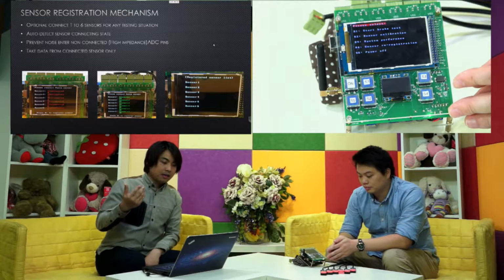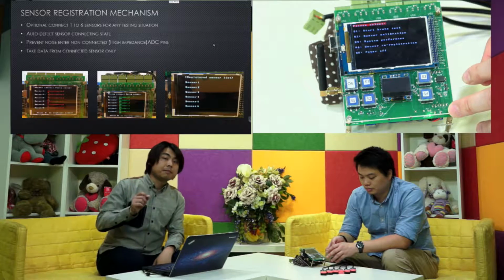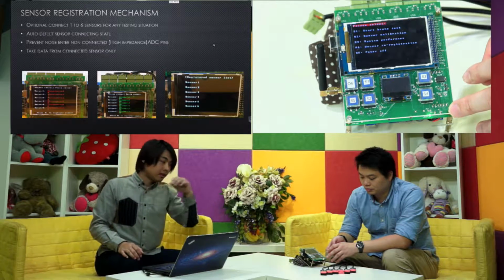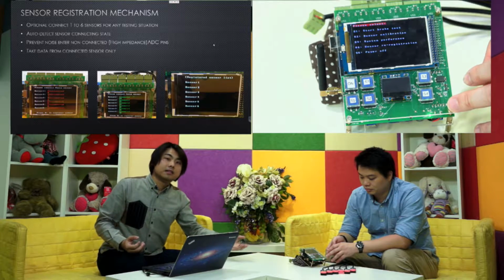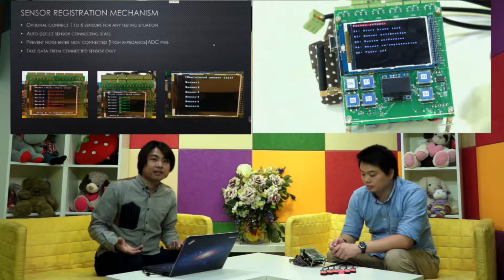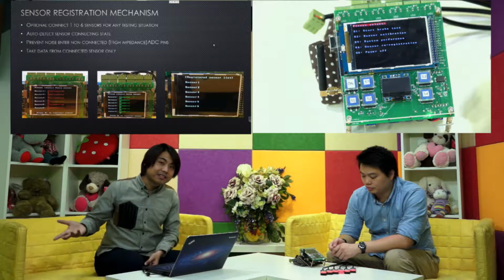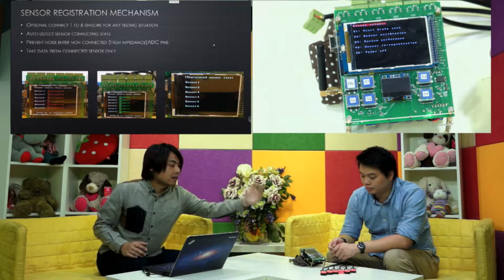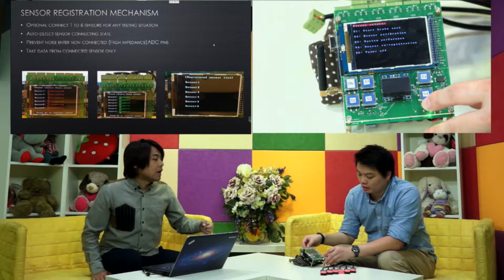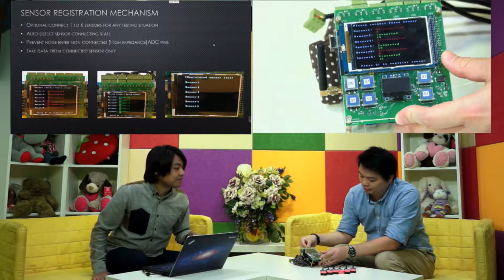Okay, why do we adopt this mechanism? Because you may consider the ADC: if you do not connect the sensor, the ADC pin is in high impedance. In high impedance, maybe some EMI will enter the ADC pin and add noise to the force curve. Those data are useless, and we don't want to save the data, and we don't want to transfer it into the database. So this mechanism prevents useless data when you do not connect all the sensors. That means this device has the ability to use 1 to 6 sensors, chosen by the user. Okay, now we connect all the sensors to the system again, for the other testing.